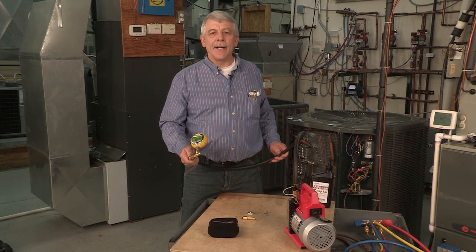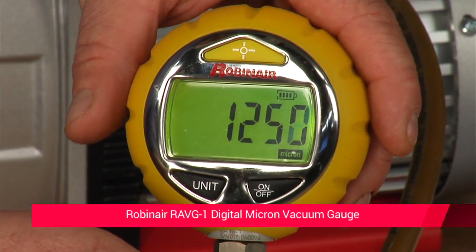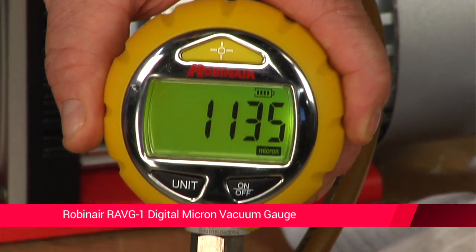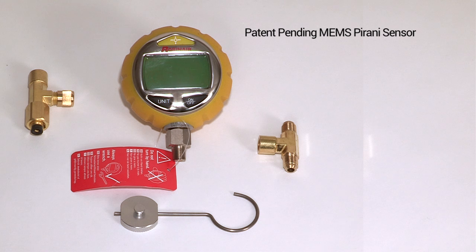is a must-have for every HVAC technician's toolbox is the digital micron vacuum gauge. Robinair recently introduced one of the most sophisticated digital micron vacuum gauges available for field service. The RAVG1 employs a sophisticated patent-pending MEMS Pirani type sensor that directly measures vacuum level.